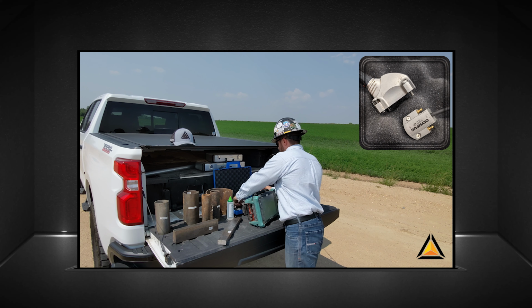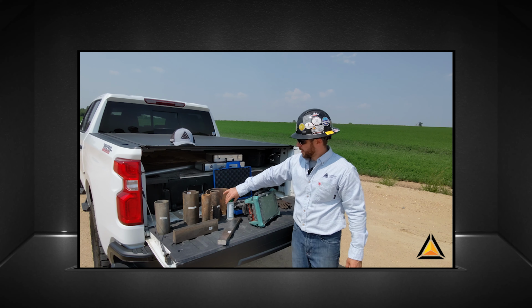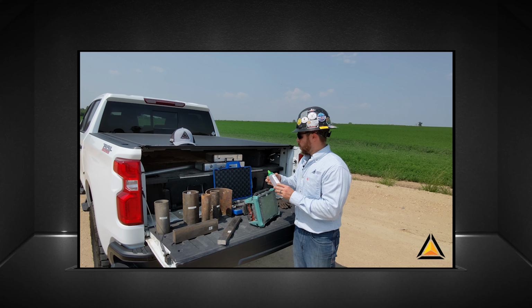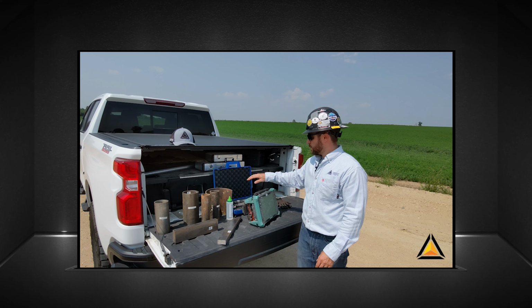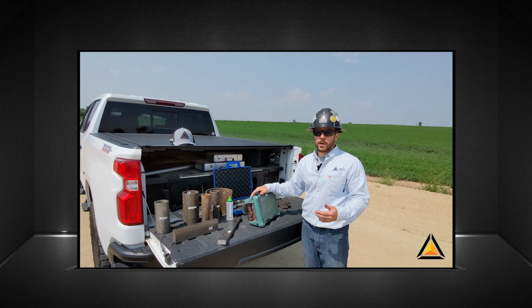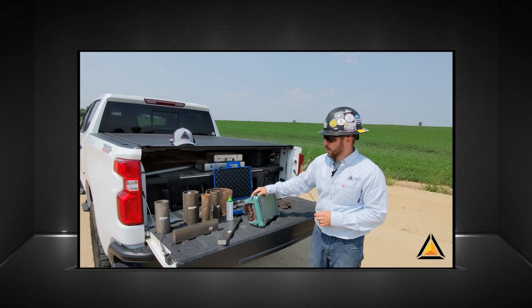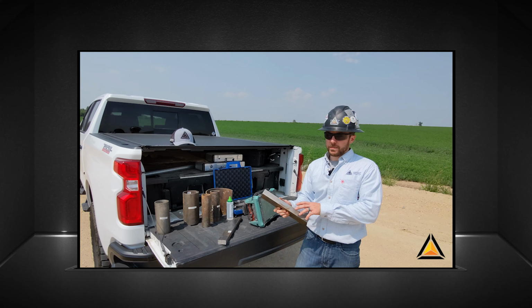Now, once we've chosen the proper combination of probe and wedge, we adhere them together with ultrasonic coupling. What this does is it eliminates any air gap in between the surface of the probe and the wedge, allowing for sound to pass through without issue. Once that's completed, we move on to the calibration.